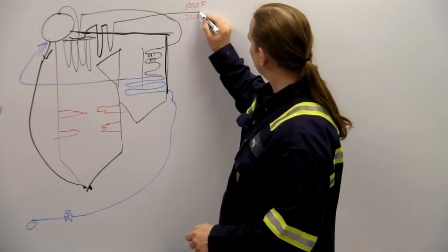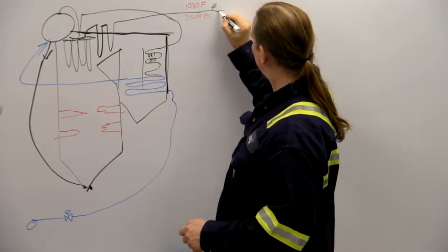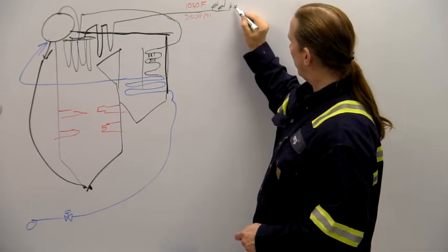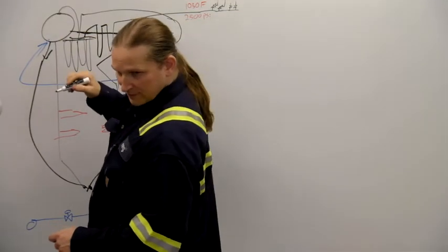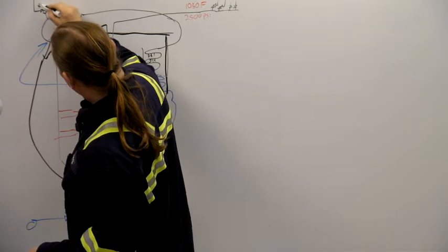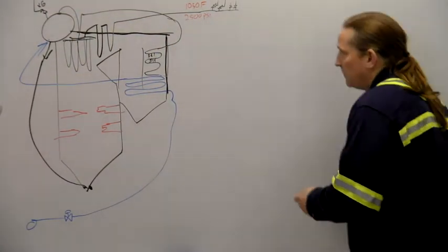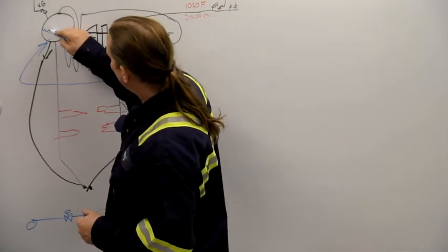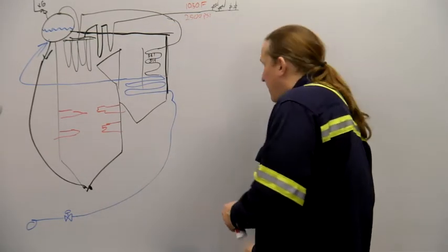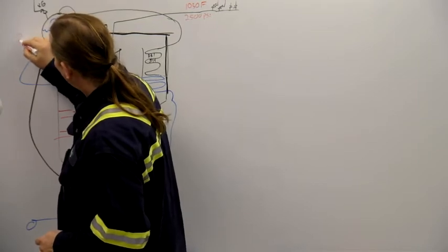Let's see. I guess I gotta squeeze it. Got relief valves. And then we got the power operated relief valves, which are air-operated, and he controls them from the DCS. Let's go back to the drum. We've got six. Oh, yes, there are six relief valves on the drum as well. Let's draw drum level. Steam. And here we are talking about 2,500 PSI and 1,050 Fahrenheit.